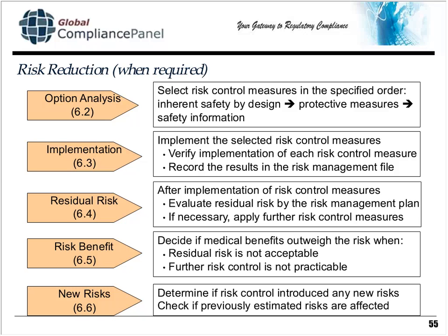We're going to answer the question, does the benefit of this medical device for this hazard I'm analyzing outweigh the risk associated with that same hazard? And then when I get through all of that, I'm going to ask the question, have I introduced any new risks? Because remember, I've had to change the design.